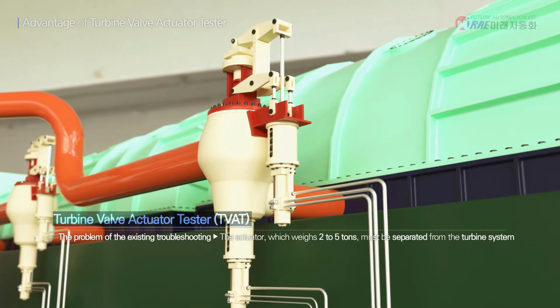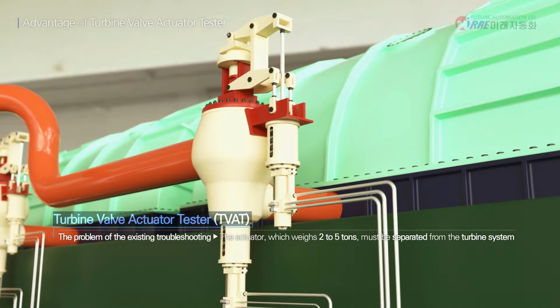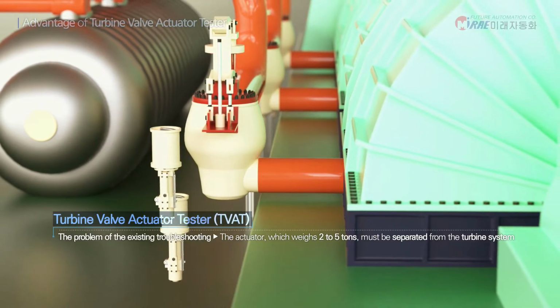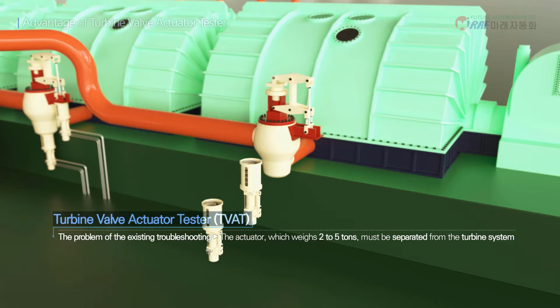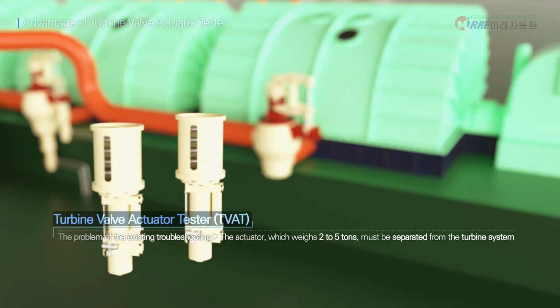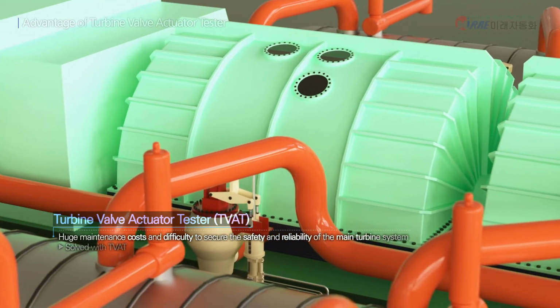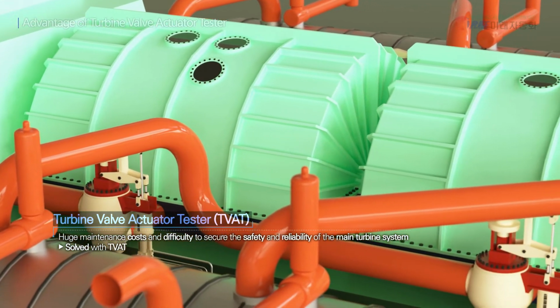The problem with existing troubleshooting is that the actuator, which weighs 2 to 5 tons, must be separated from the turbine system. As a result, huge maintenance costs were incurred, and it was difficult to secure the safety and reliability of the main turbine system.